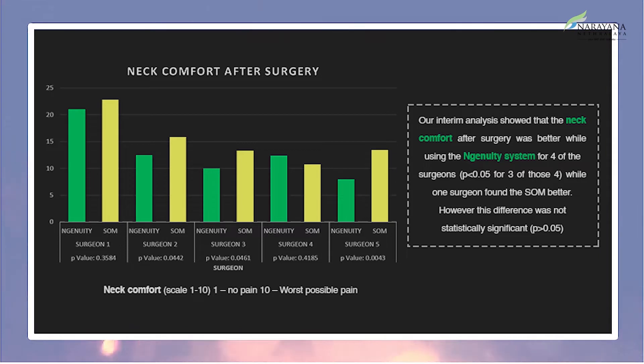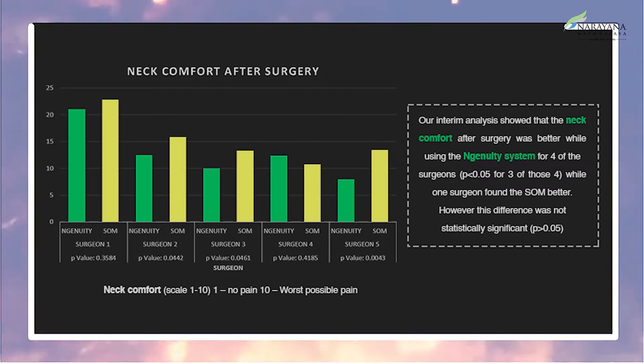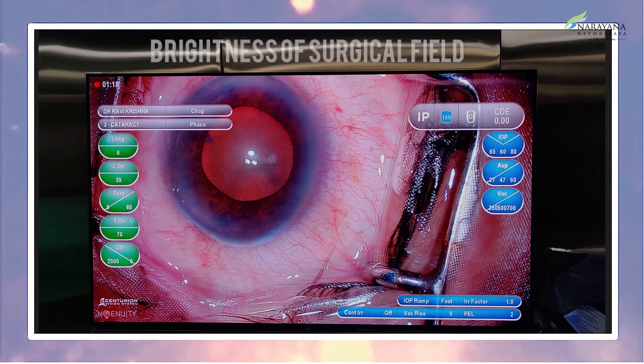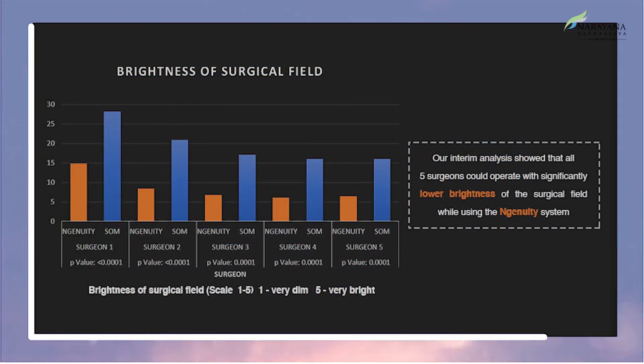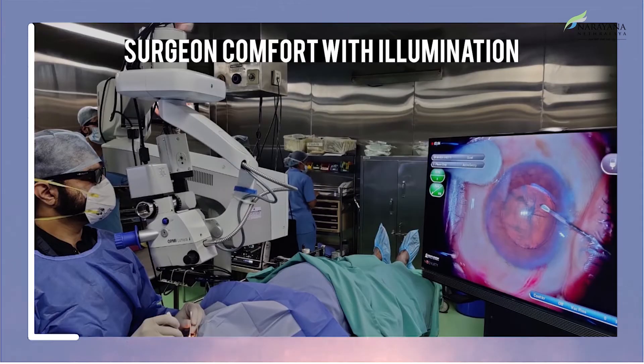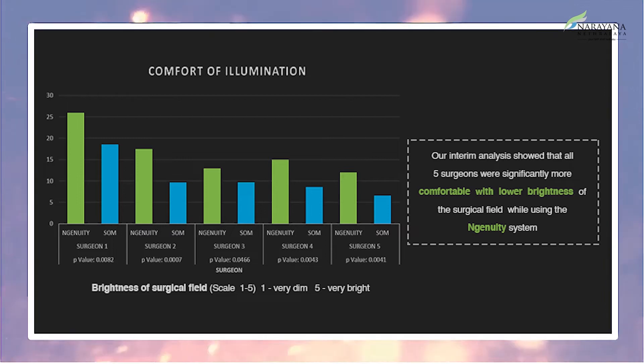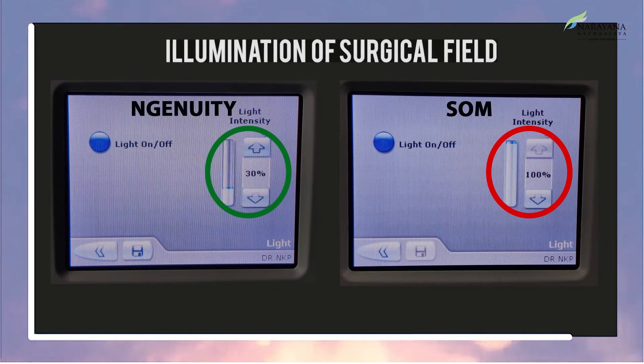Our analysis showed that neck comfort after surgery was better while using the Ngenuity system for four of the five surgeons, and for three of them it was statistically significant. One surgeon found the standard operating microscope more comfortable, but this was not statistically significant. All five surgeons could operate with significantly lower brightness of the surgical field while using the Ngenuity system, and all five were significantly more comfortable with this lower brightness. The Ngenuity system also required significantly lower illumination, which led to better patient comfort and cooperation.